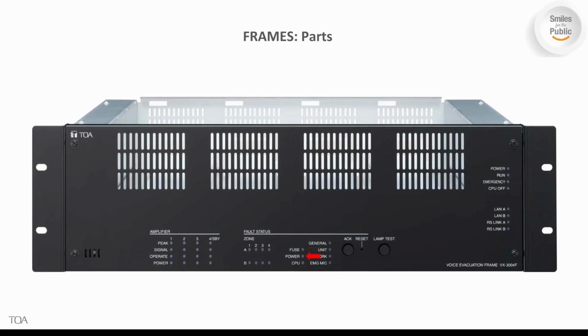The power fault indicator LED lights up yellow when there is a supply issue detected via the RS-Link connection. The CPU fault indicator LED lights up yellow when there is a CPU failure in the system. The general fault indicator lights up yellow when there's a general failure detected in the overall VX3000 system.